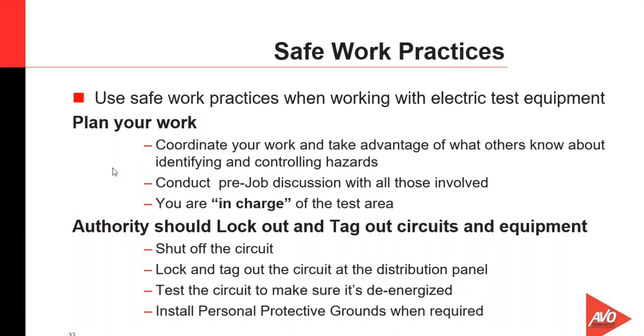The authority having jurisdiction over lines and equipment, we may, as a tester, not be responsible for switching and clearing, but certainly responsible for verifying that the system is dead. But whoever is responsible would go through a process of switching, clearing, locking out, tagging out, verifying that the system is de-energized, and possibly installing personal protective grounds as required.